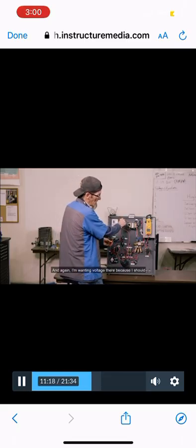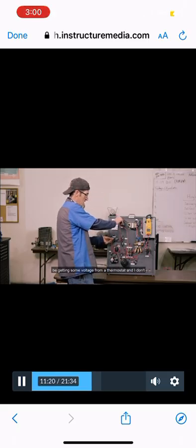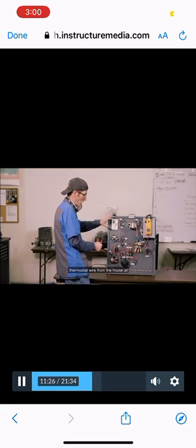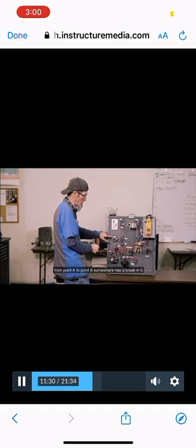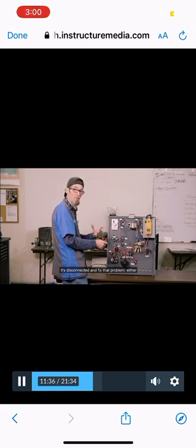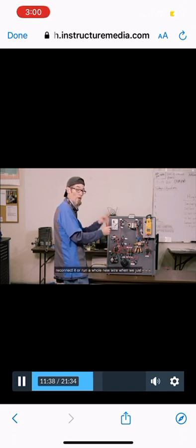And again, I'm wanting voltage there because I should be getting some voltage from my thermostat, and I don't have any voltage. So that means that I have a broken thermostat wire from the house all the way up to the unit. So this little wire right here from point A to point B somewhere has a break in it. So I would have to try to find where it's broken, where it's disconnected, and fix that problem. Either reconnect it or run a whole new wire.